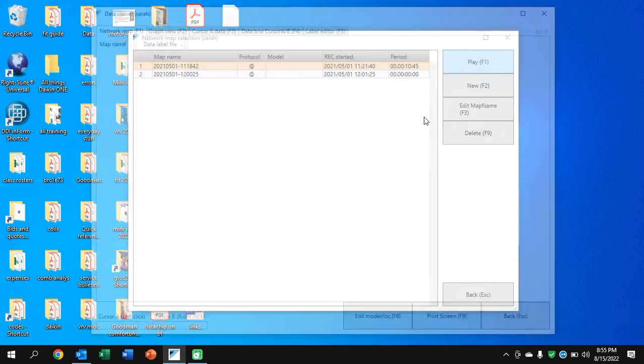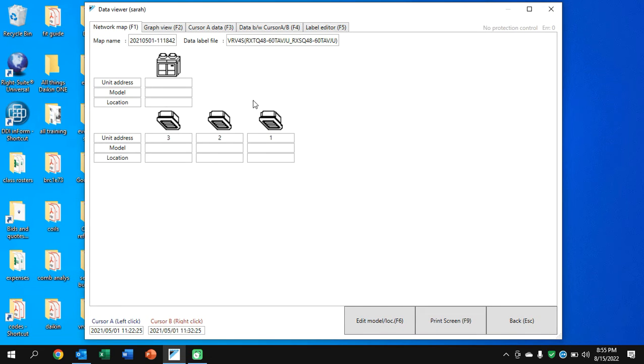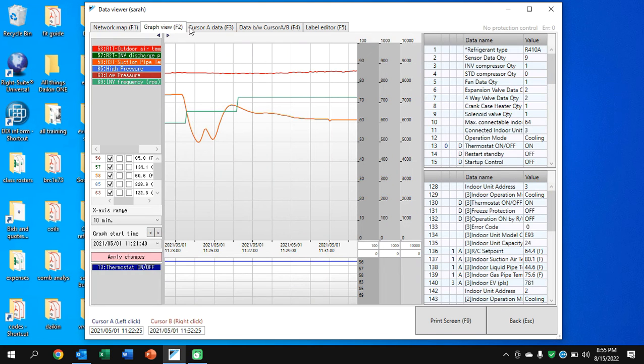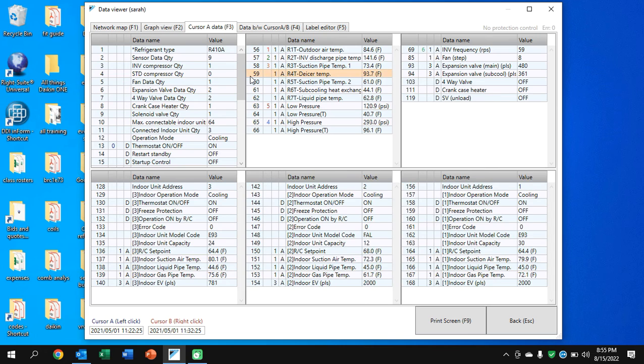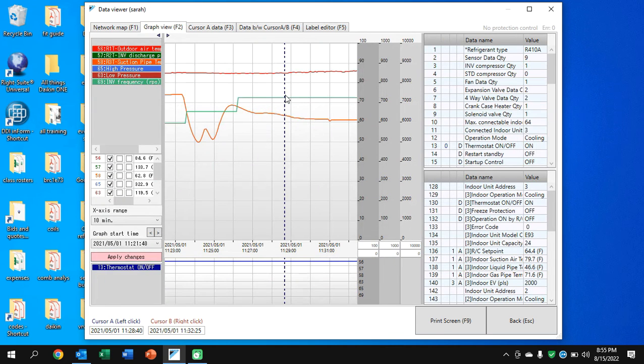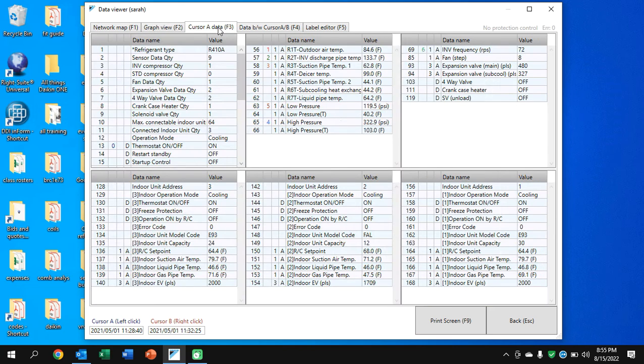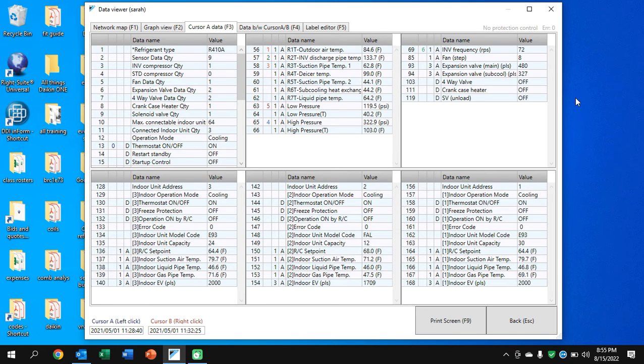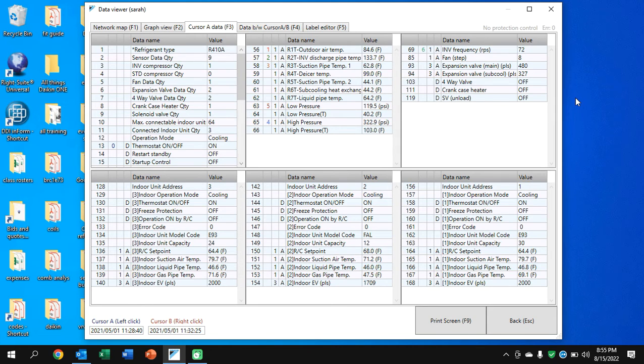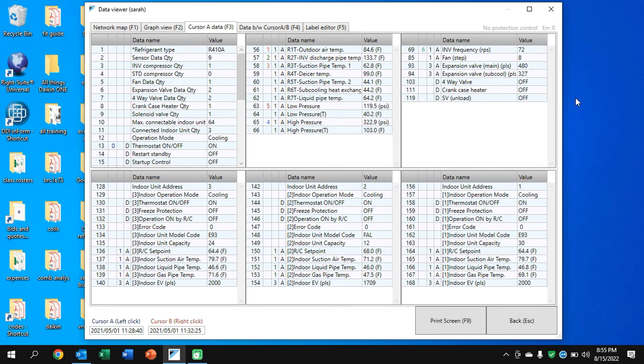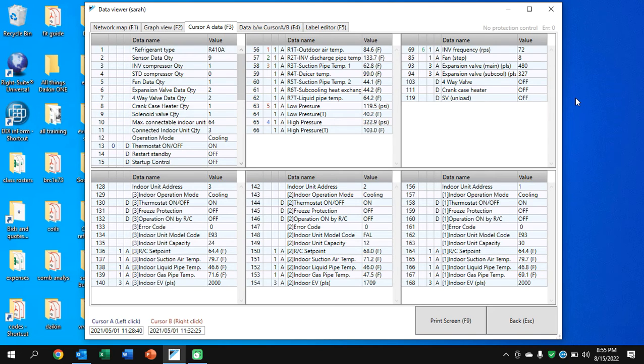All right. Let's go ahead and just take a look at a VRV. I come in here and we'll do a VRV under graph view. And we'll see a few items. But what I want to really point out to you is those are the only ones I have turned on right now. But we go along the timeline and we'll go into the cursor data. And we'll try and pull up some data. And a few things here. You'll see I've got external expansion valves in the outdoor unit as well as the indoor unit. And they operate for different reasons. On the commercial VRV, we'll see up to seven, I think, expansion valves in some of the equipment, mattering what we're doing with the equipment. And you'll notice the indoor heads. And what you really have to note when you touch your VRV is we'll look at the superheat and subcool. That's always great to look at in your pressures.